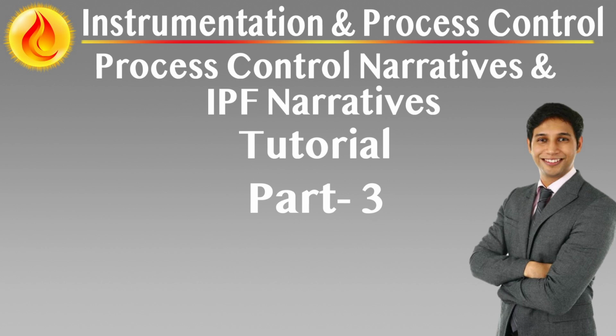Scope and applicability. Alarm narratives are required for all operator actionable alarms with the exception of trip alarms, which are covered under IPF narratives and logic, and pre-alarms, which are used to alert of impending trip conditions but are not treated as operator-controlled protective layers. Each alarm is documented individually even when multiple alarms originate from the same instrument, e.g. a transmitter with both high and low limits, because each condition typically demands a different response and serves a different operational role.